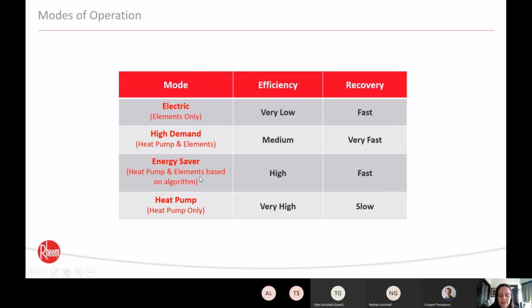Energy saver mode, again, that's the default. It's going to utilize the heat pump and the elements as needed. High efficiency with the fast recovery, and then heat pump only, not utilizing the elements at all. So really in your heat pump, you're utilizing only 300 to 400 watts of power. Very, very efficient, very good fit if you're combining with solar, right? Very, very high efficiency, but again, a slower recovery, anywhere from 1,200 to about 2,000 watts of recovery.